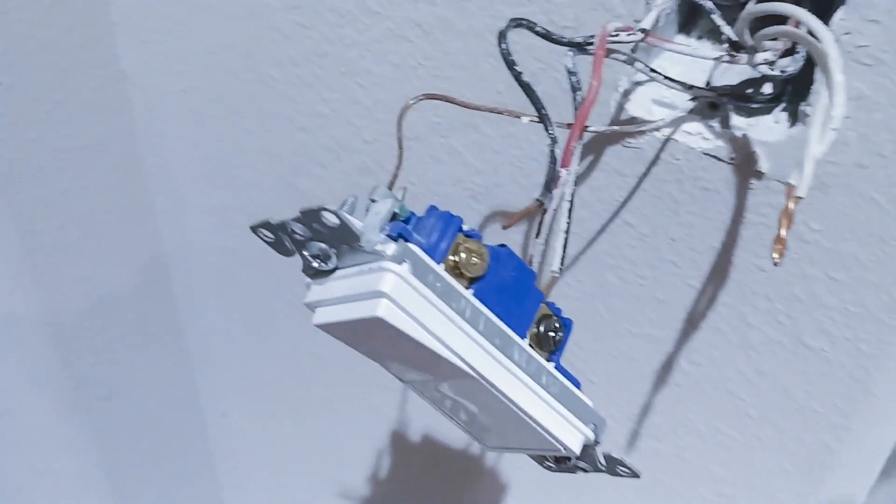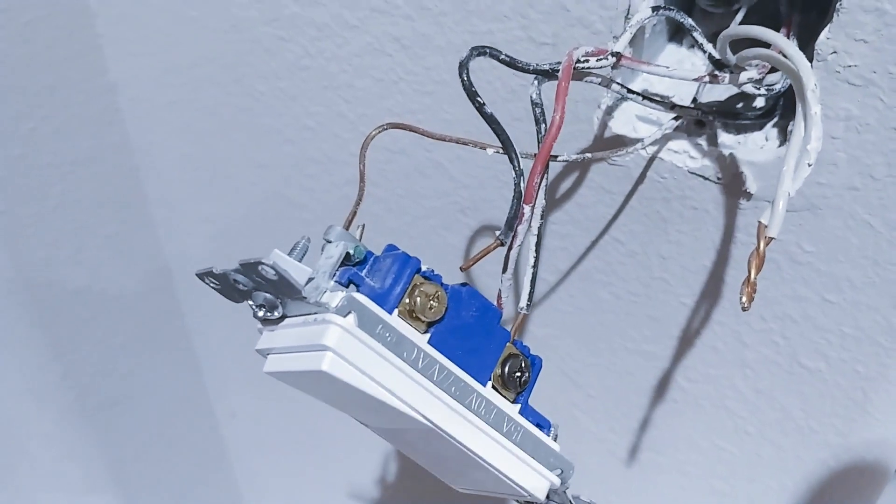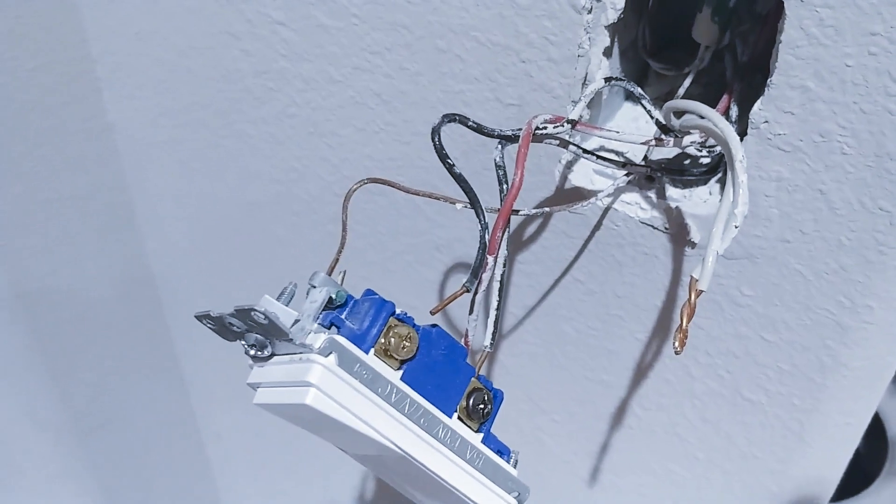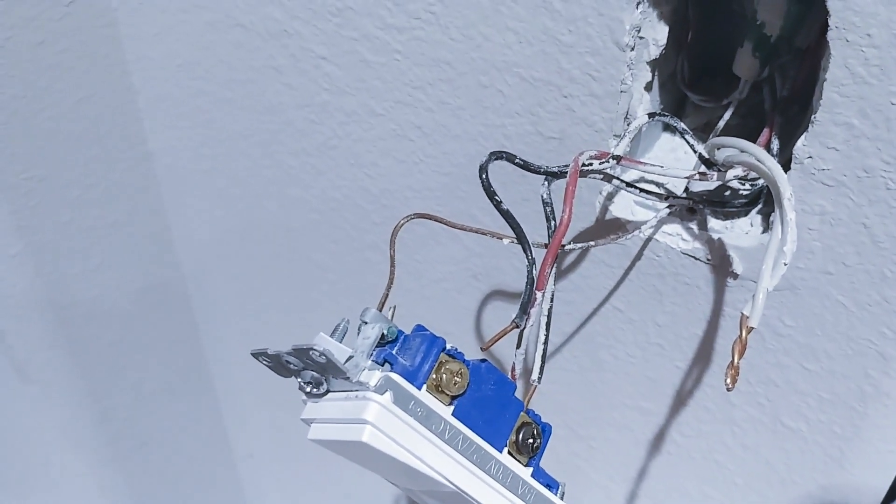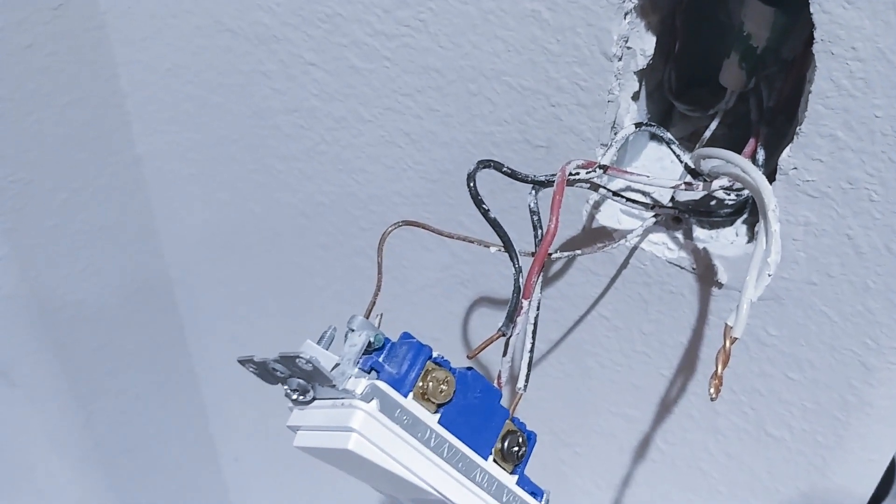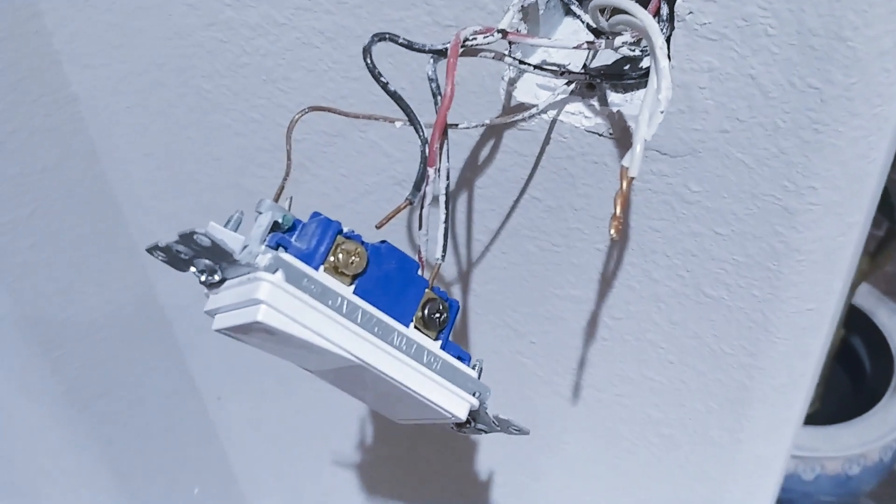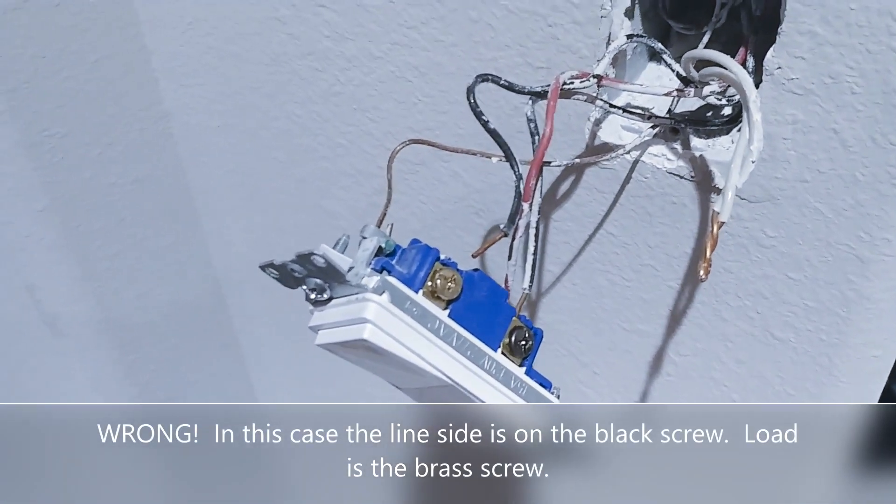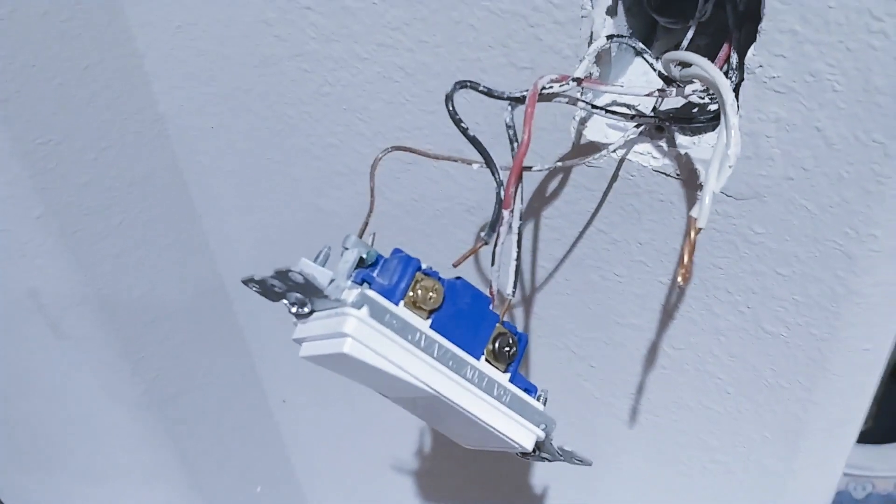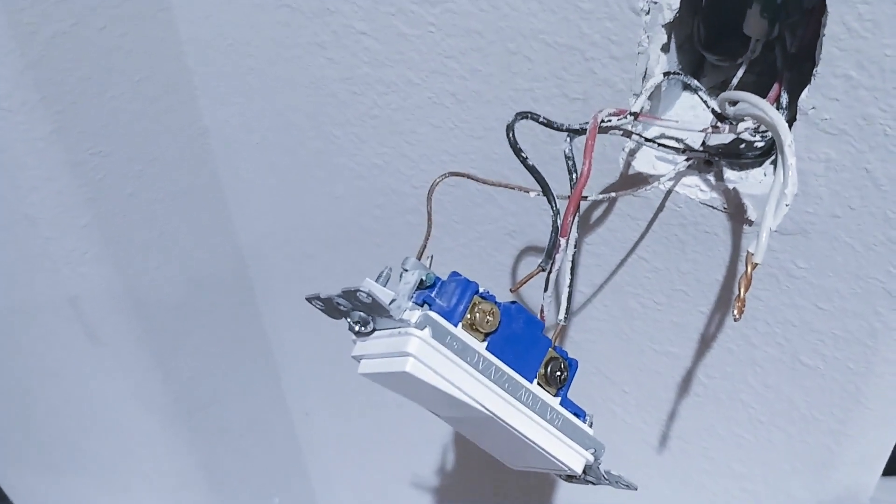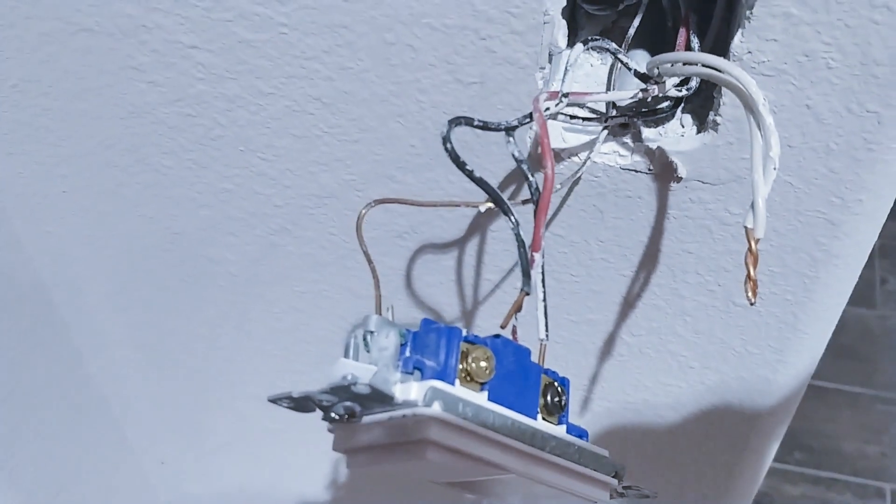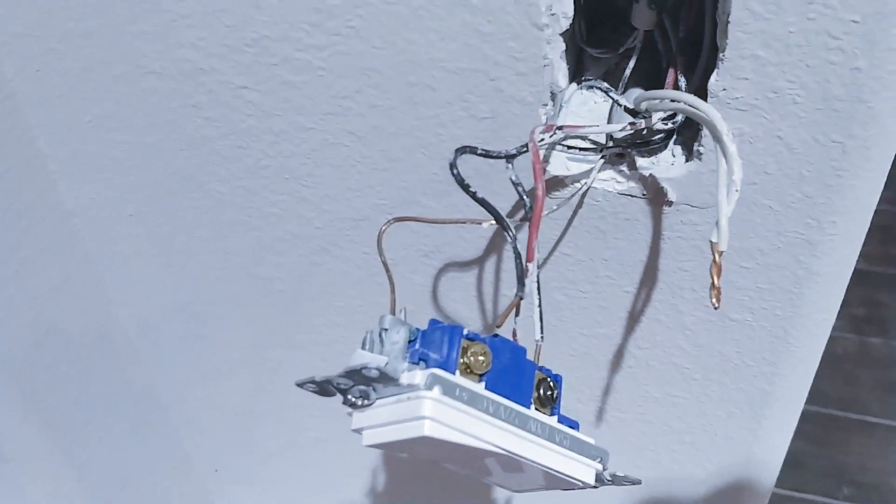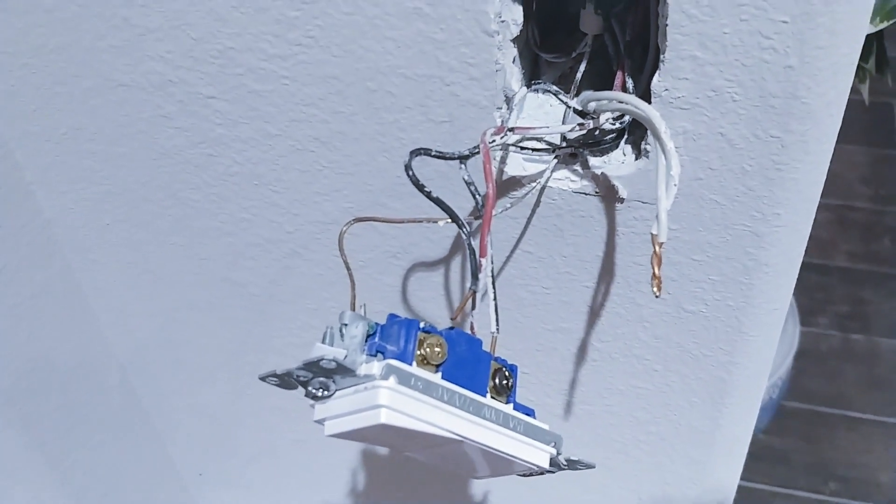Another thing I want to note is when you look at these things, look at the colors of the terminals if you can, that can usually help. Typically the line side or the side coming from the other switch is going into the gold terminal. The black is typically going to the load and that's important because they're the same color so you don't really know what's going to what. The color of the terminals really helps. I'll probably mark that to make sure I don't lose that. And then the red is obviously another traveler wire. So that's how I'm going to wire this thing up and I will show this all off in the schematic.